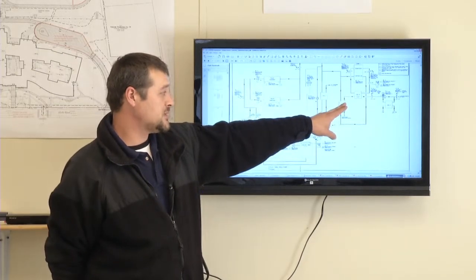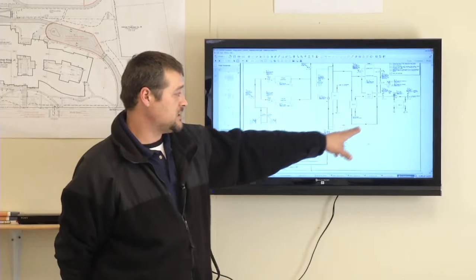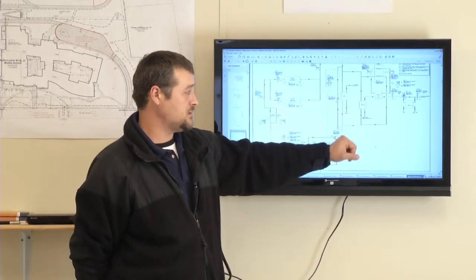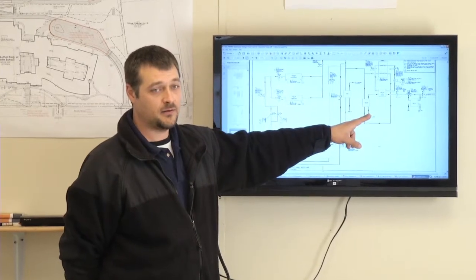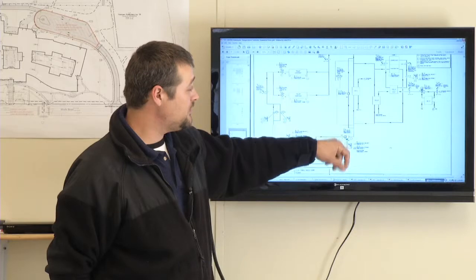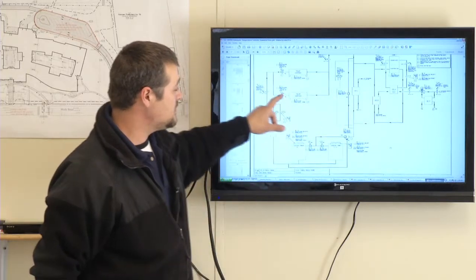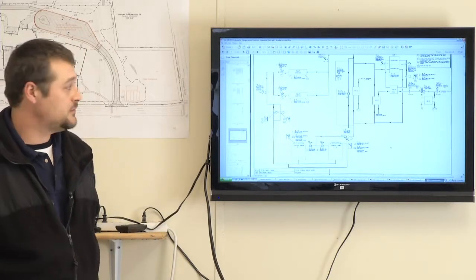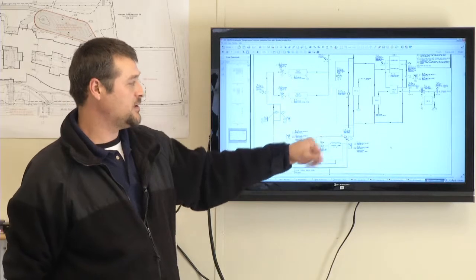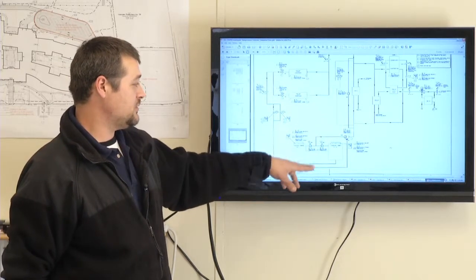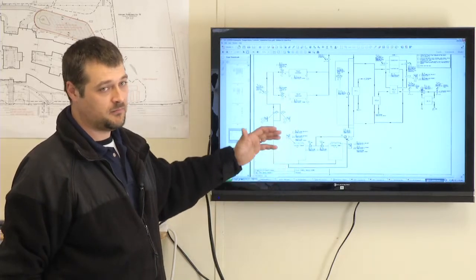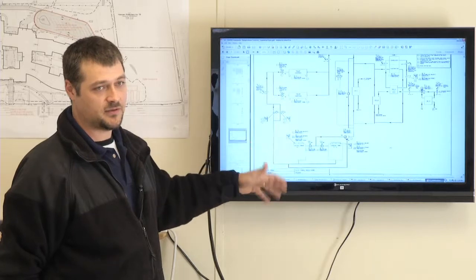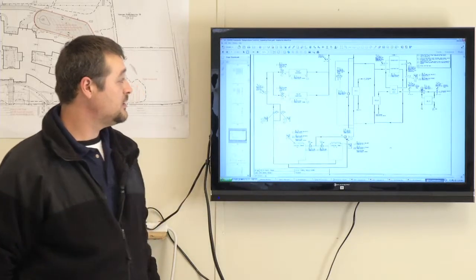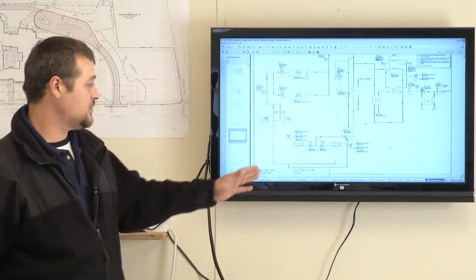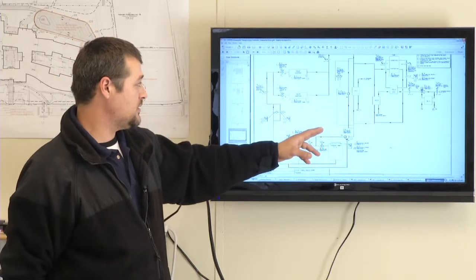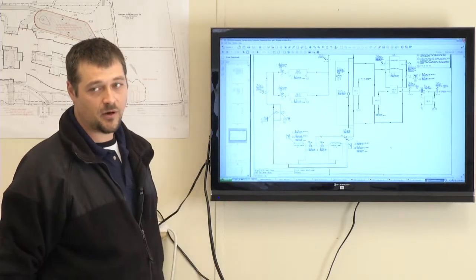This has a fairly low set point, and if the domestic water system is up to temperature on the leaving side of heat exchanger 3 or heat exchanger 4, this unit is going to back down and will likely shut off. Right now it's got a set point of 44 degrees on its evaporator coil, which is the condenser loop to chillers 1 and 2. So generally speaking, once the chillers are enabled, the heat recovery starts up, the temperature of the condenser water drops rapidly. The chillers are bypassed at that point, and typically everything sits at minimum until the load resumes on the system. So you will see a fluctuation sometimes between the heat recovery turning off and on, and then your cooling towers with a ramp up or down.